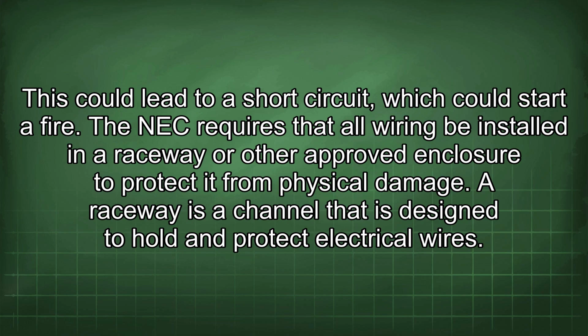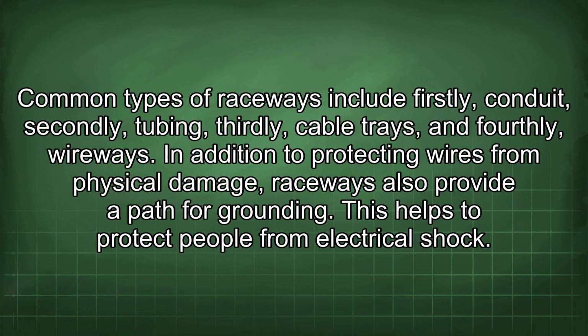The NEC requires that all wiring be installed in a raceway or other approved enclosure to protect it from physical damage. A raceway is a channel that is designed to hold and protect electrical wires. Common types of raceways include firstly, conduit, secondly, tubing, thirdly, cable trays, and fourthly, wireways. In addition to protecting wires from physical damage, raceways also provide a path for grounding. This helps to protect people from electrical shock.